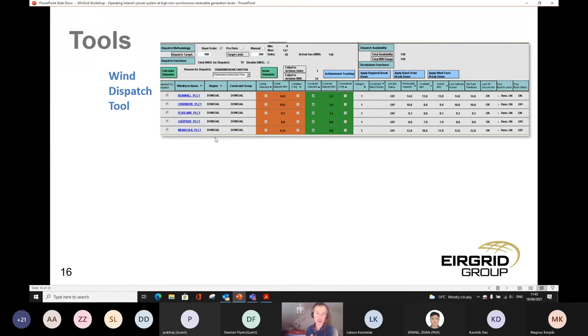So we can do that for individual groups, but we can also do it for essentially the whole system as well. If we're coming up against, say, close to 75% SNSP on the system, and the wind is continuing to increase, we can select essentially every wind farm in the country and apply, say, a 100 megawatt reduction in the collective output of all those wind farms. The tool calculates the individual set point of each wind farm and issues it to the wind farm control system, and we get our 100 megawatt reduction pro rata across the entire system. So this is a really powerful tool and very important to us in the control centers.